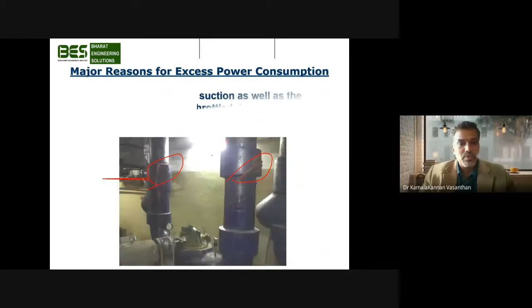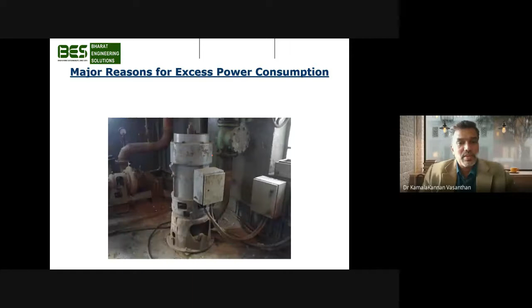The other key reason we find for excess power consumption is old and inefficient pumps. We visited a site and were discussing with the maintenance team. We had made the site study and a preliminary audit with the plant, and we said we would like to check your other parts too, like water intake and water distribution. He was very confident and stated that he has a pump which has been running for 20 years plus, with not a single failure or replacement, not even a variant from the mechanical seal. We were surprised and visited the site, and we saw that it was operating at only 25 to 26% efficiency, and had been running like that for 20 years.